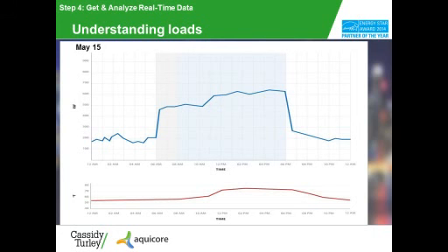So the first thing I would look at, if this were in front of me, is the base load. The base load is this portion right over here on the left. And I talked a little bit earlier about understanding those high points and those low points. So what happened around 3 a.m. or 2:30 a.m.? What caused that rise in energy use? Was something running that we wouldn't expect to be running? Something that could be turned off? Could it be building hot water, domestic hot water that's reheating itself, and really we could secure that? Is it water coolers? Is it elevator use by security? Just understanding what that load is.